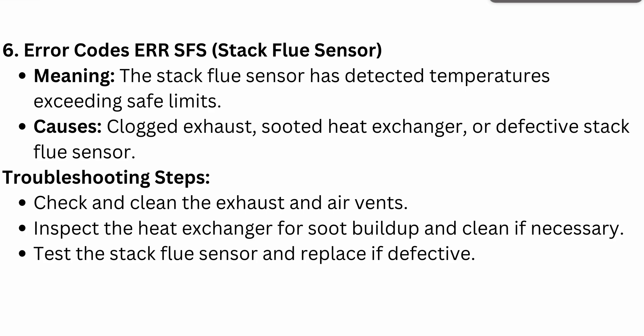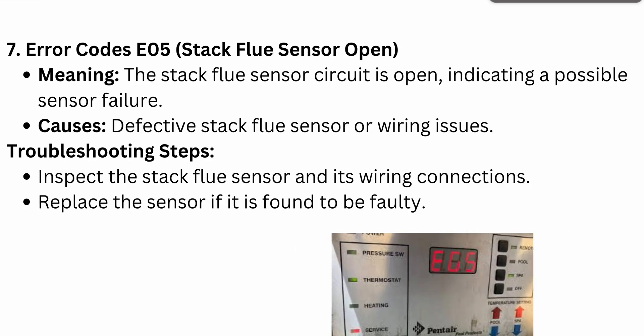Error code E05 is stack flue sensor open. It means the stack flue sensor circuit is open, indicating a possible sensor failure. The causes can be a defective stack flue sensor or wiring issues. The troubleshooting steps are to inspect the stack flue sensor and its wiring connections, and replace the sensor if it is found to be faulty.